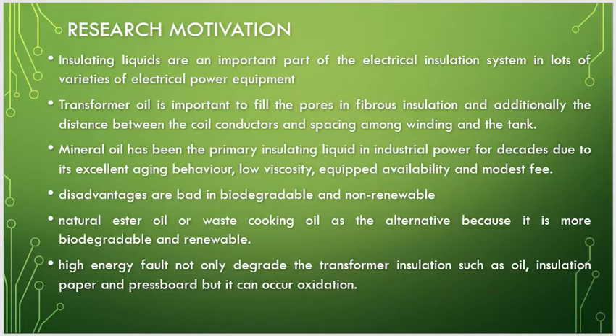And then about mineral oil behavior: low viscosity, equal availability, and modest fee. The disadvantages are that it is not biodegradable and non-renewable. Then natural ester oil or waste cooking oil is the alternative because it is more biodegradable and renewable. A high energy fault not only degrades the transformer insulation such as oil, insulation paper, and pressboard, but oxidation can occur.